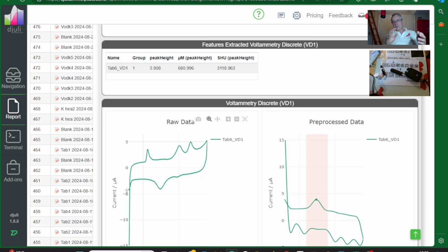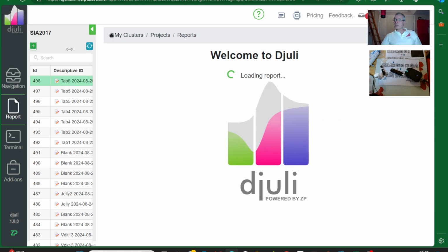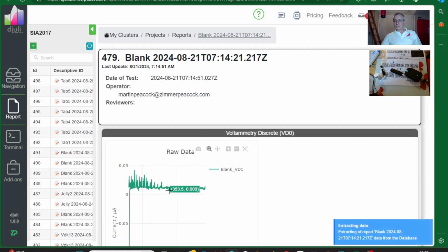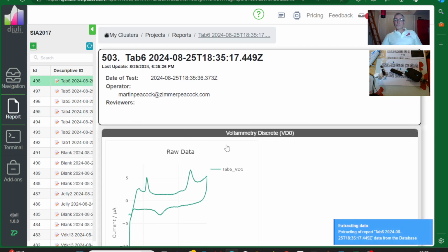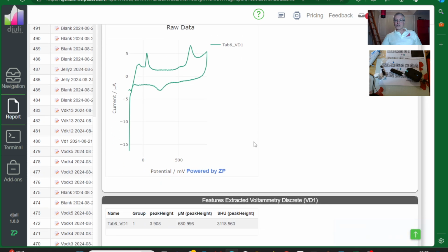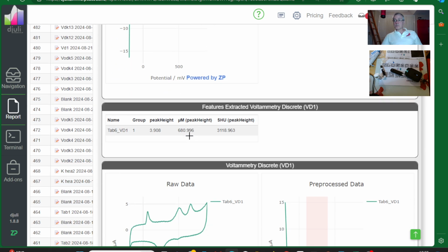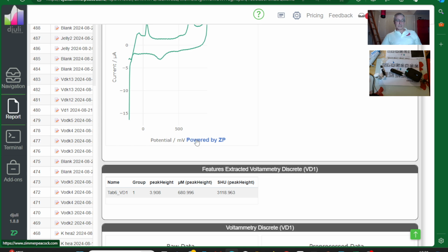If this machine was, let's say, messing around or breaking, I'll have a quick look here now. This is data where I put no sample onto it. But the raw signal is almost like a health indicator that this machine is still operating well. So you can always check yourself for your client, or you can share the data with ZP as well, and ZP can check it. So the answer to your question is this is not operating the same way as a pH sensor. A pH sensor is using a method called potentiometry. This is actually using a patented technique called cyclic voltammetry.